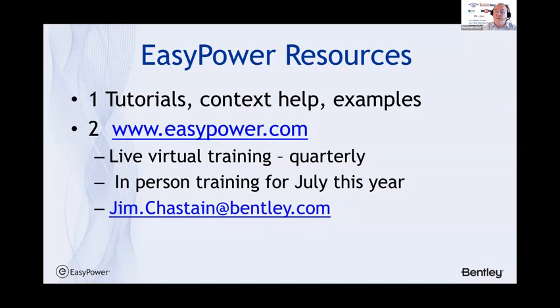Okay, how often do arc flash labels need to be updated, and why do they have to be updated if the equipment has not changed its configuration? Good question. They don't have to be updated if it hasn't changed. They do have to be reviewed. The status has to be reviewed every 5 years of the overall assessment, or anytime there's a change that affects the calculations or the results.